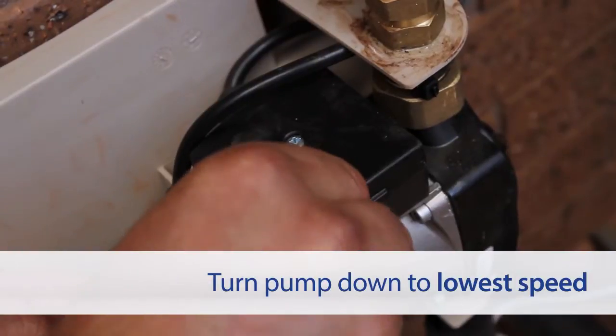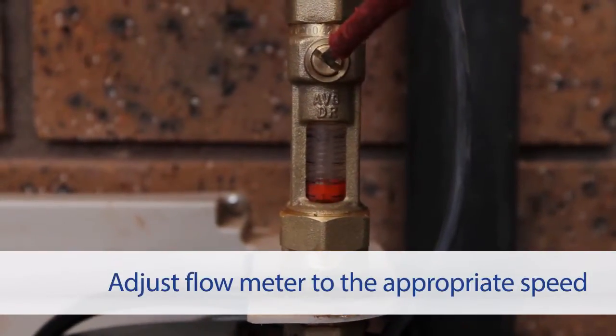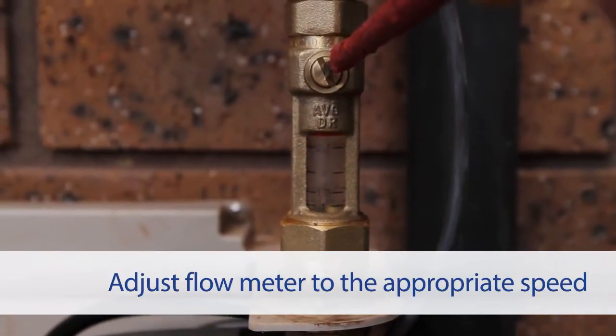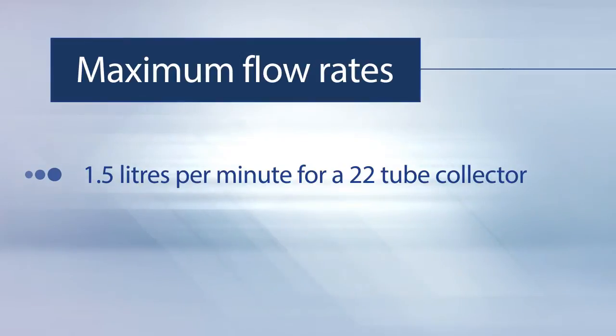Turn the pump speed down to its lowest speed. Adjust the flow meter to the appropriate speed based on the collector size. The maximum flow rates are 1.5 litres per minute for a 22 tube collector.